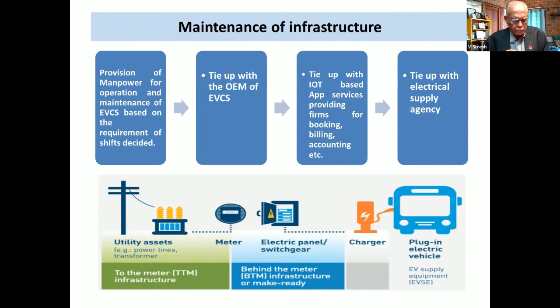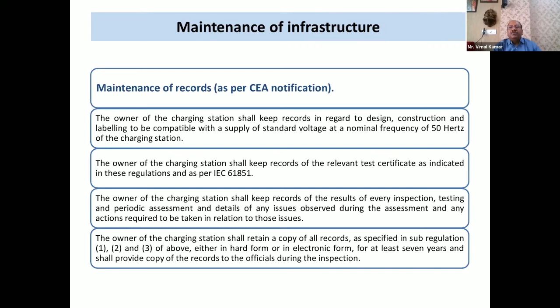This maintenance is part of the CEA notification, which says the owner of the charging station will keep records regarding design and construction, keep test certificates, keep records of results of every inspection, testing and periodic assessment, and retain copies of all records as specified in the sub-regulation. So maintenance of the infrastructure is covered under these guidelines.